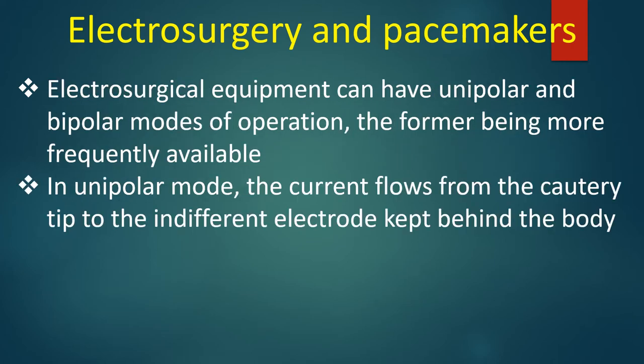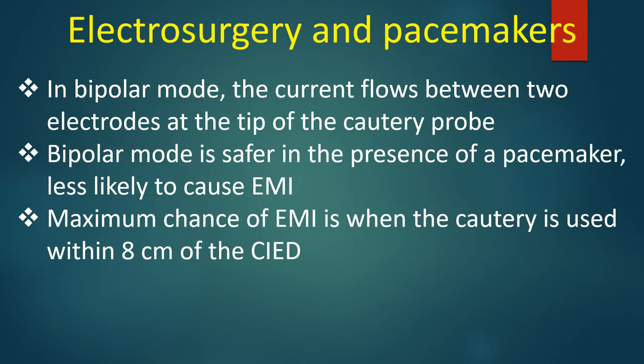Electrosurgical equipment can have unipolar and bipolar modes of operation, the former being more frequently available. In unipolar mode, current flows from the cautery tip to the indifferent electrode kept behind the body. In bipolar mode, current flows between two electrodes at the tip of the cautery probe. Bipolar mode is safer in the presence of a pacemaker, being less likely to cause EMI.